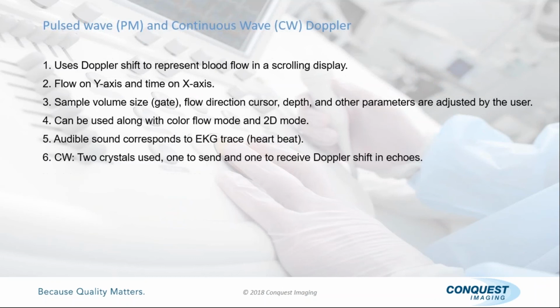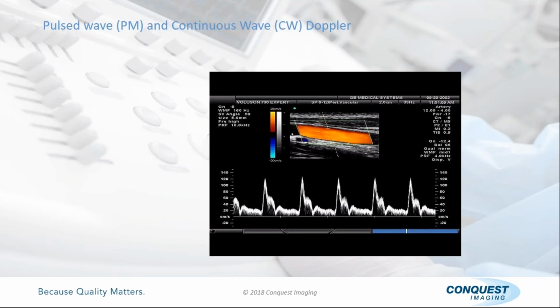Pulse wave, continuous wave, they're basically the same thing. They're trying to measure blood flow. Here's a good example of PW right here, pulse wave. Again, you can see the peaks right here. So blood flow is maxing out at about 120 centimeters per second. It's above this baseline, so it's moving towards the transducer. This color kind of indicates that it is also moving towards the transducer. So you have two different indications, both on what they call spectral data. This is color Doppler. This is spectral Doppler. So you have two different indications that it's moving towards the transducer and at what speed.